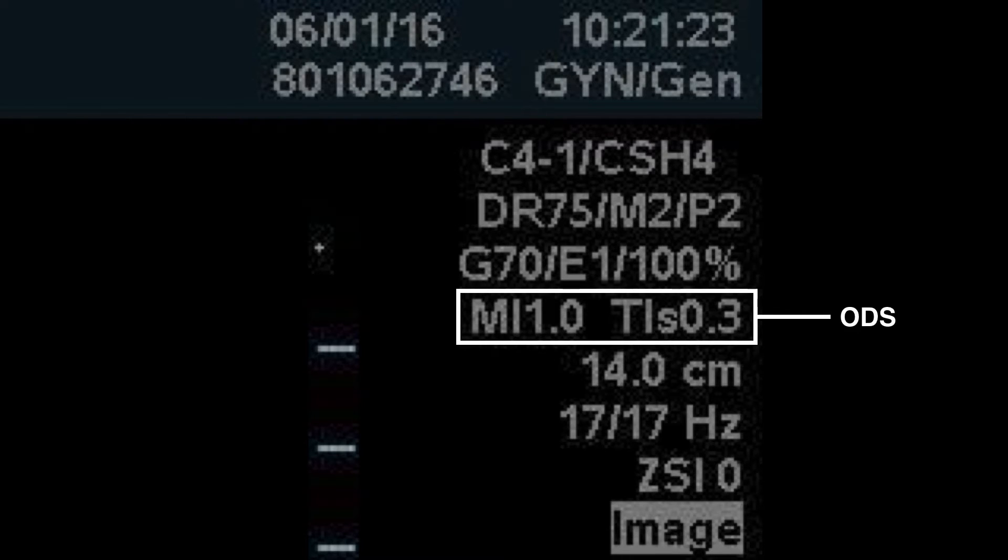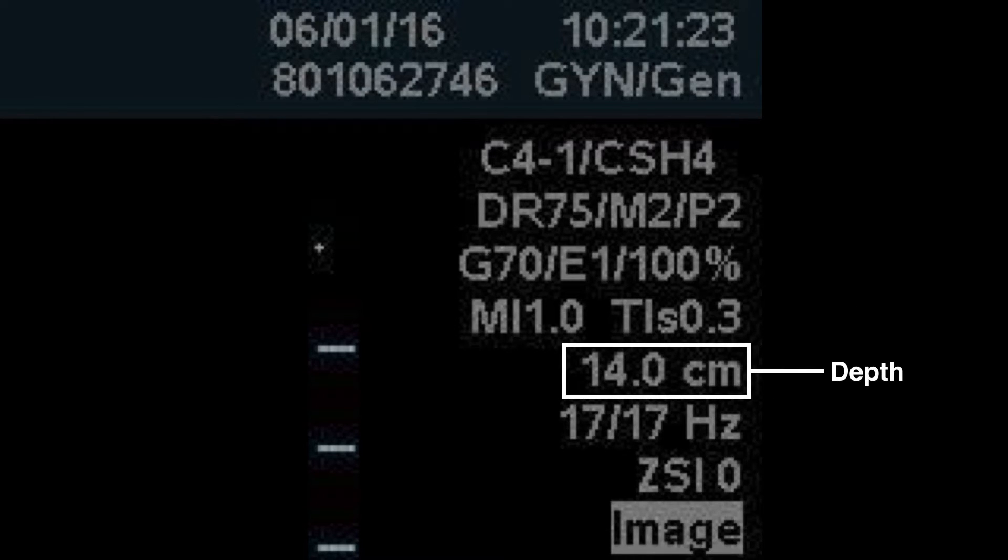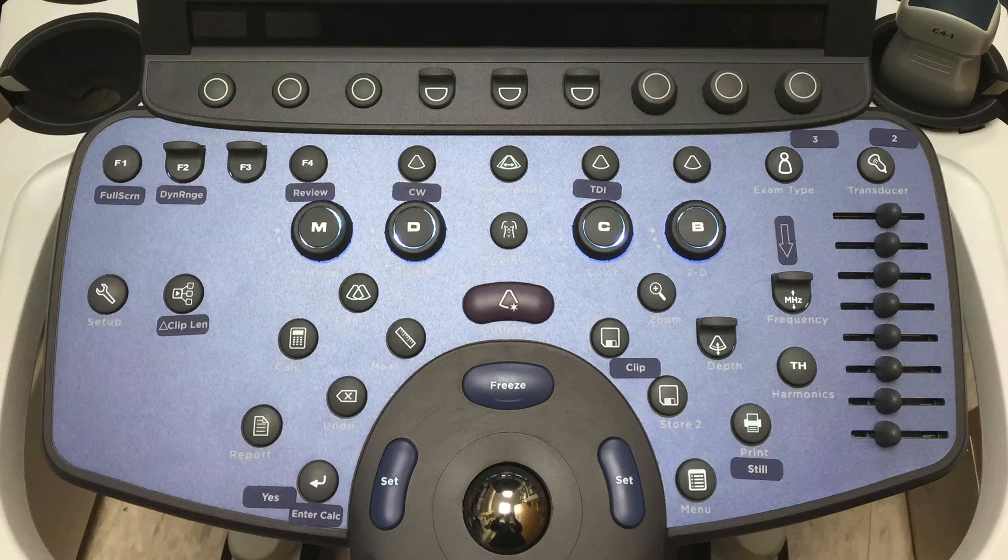You'll have the output display standard showing the mechanical index and thermal index, which is required to be displayed by the FDA. You'll also have the depth that you're imaging to — in this case 14 centimeters. Now you'll want to select the appropriate probe and preset to perform your study.